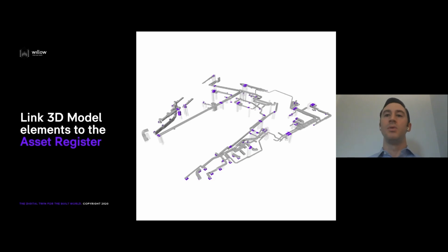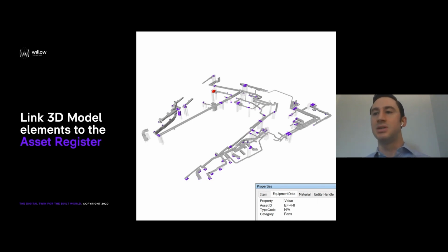One of the things we require to be included in a digital twin delivery plan, if the contractor's 3D models are going to be included in the overall digital twin, is that when you select a specific piece of equipment considered a digital twin asset, you're able to see in the Navisworks properties that this is an exhaust fan, this is the category it belongs to, and this is its asset ID or equipment tag number.